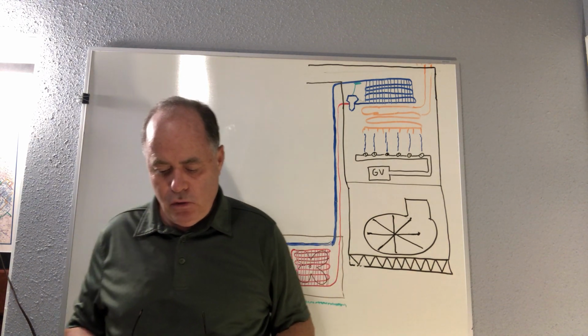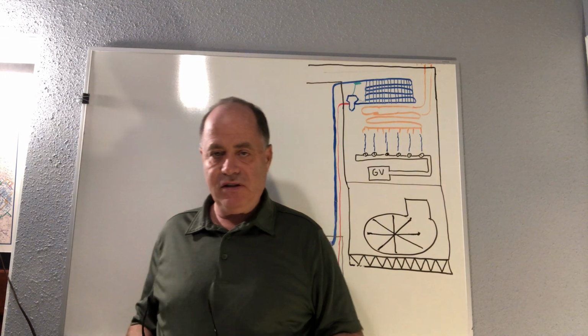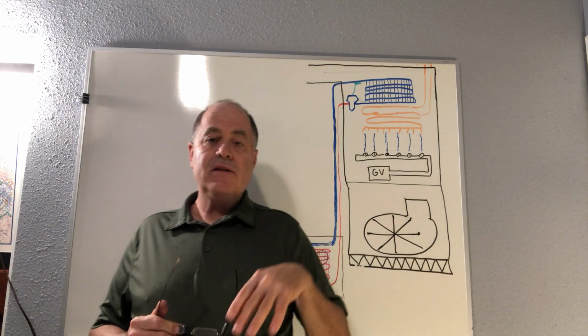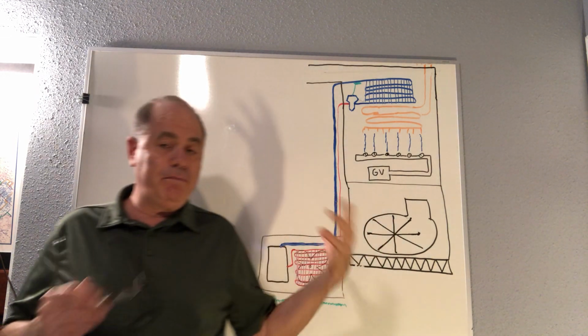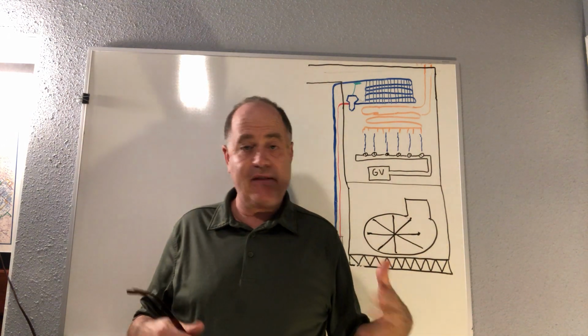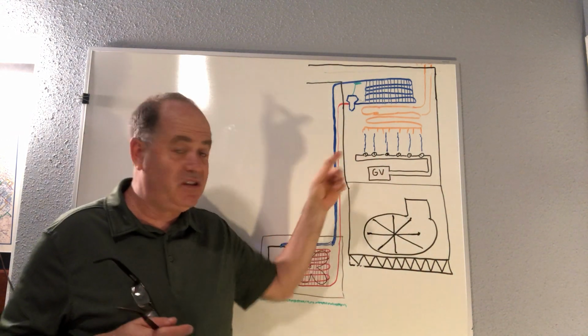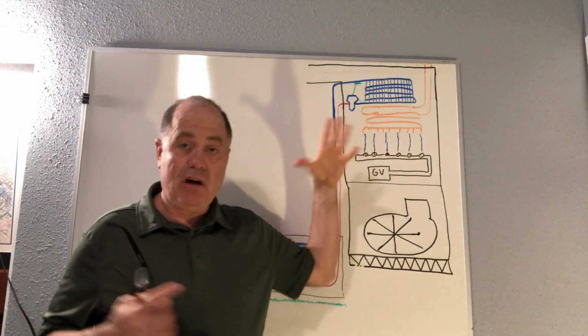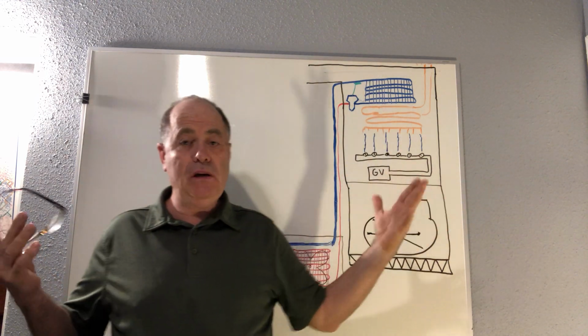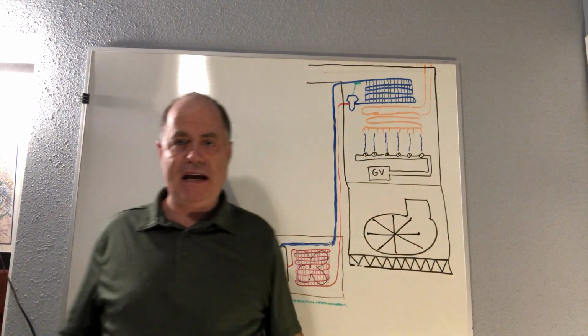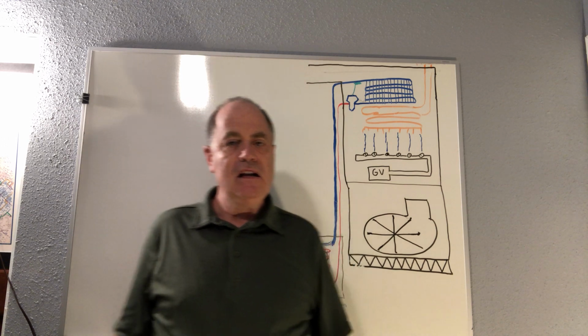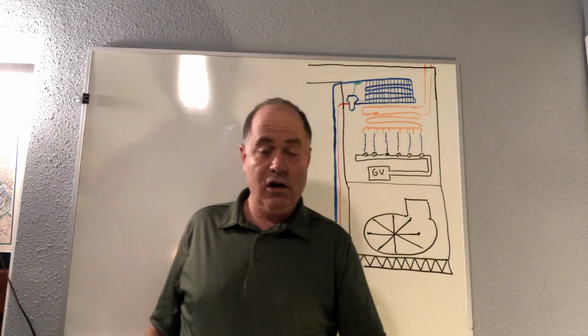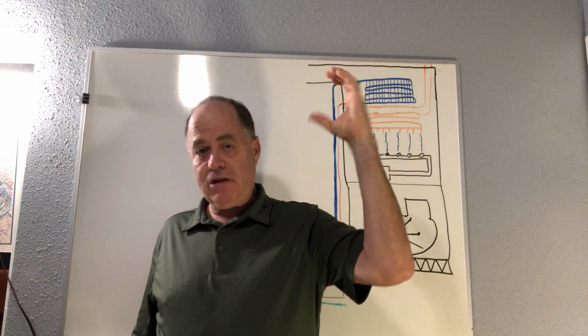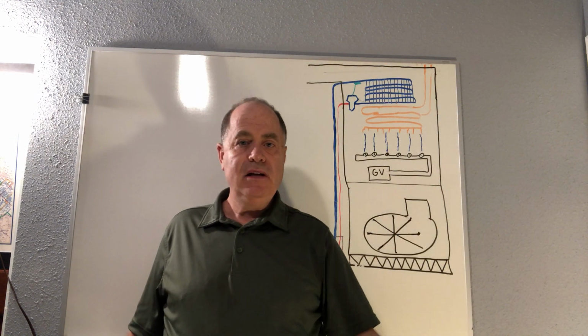Okay. Also, for pressure relief valves, this is where I've hesitated. You have overpressure. If something were to happen and everything went wrong and a gas valve stayed stuck open while the flame was on, the only way to stop that would be to manually shut the gas supply off. Okay, so if all that goes wrong for your hot water heater at home, we have a pressure temperature relief valve that is going to discharge that.